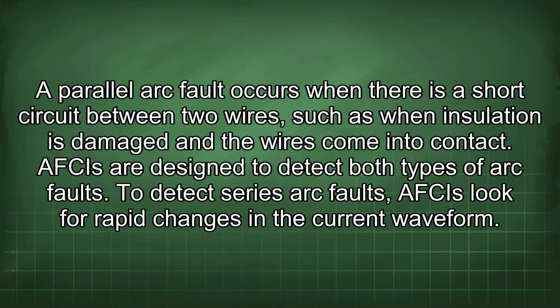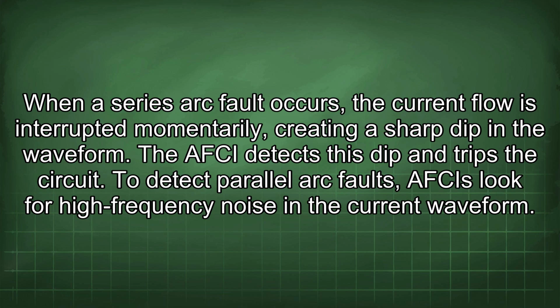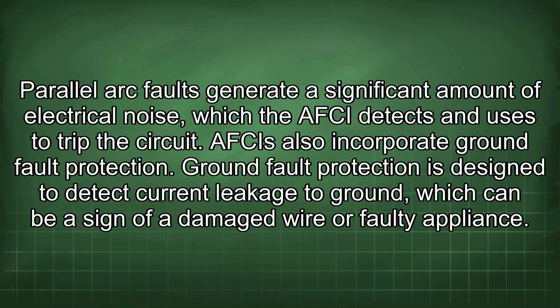To detect series arc faults, AFCIs look for rapid changes in the current waveform. When a series arc fault occurs, the current flow is interrupted momentarily, creating a sharp dip in the waveform. The AFCI detects this dip and trips the circuit. To detect parallel arc faults, AFCIs look for high-frequency noise in the current waveform. Parallel arc faults generate a significant amount of electrical noise, which the AFCI detects and uses to trip the circuit.